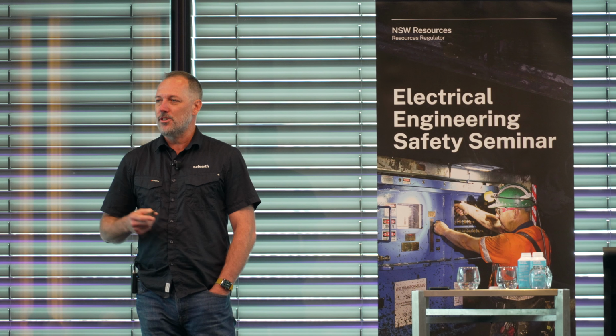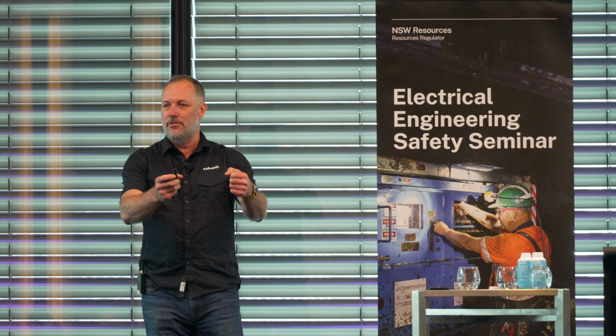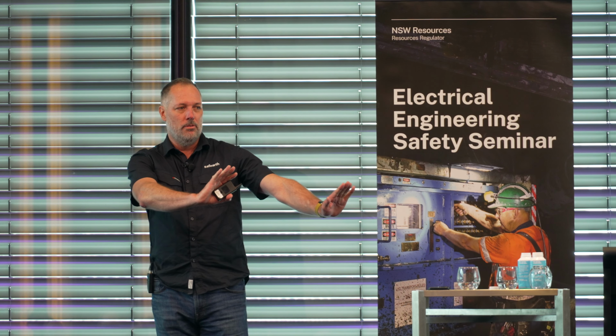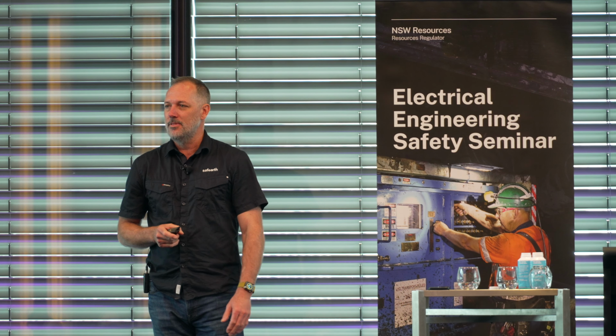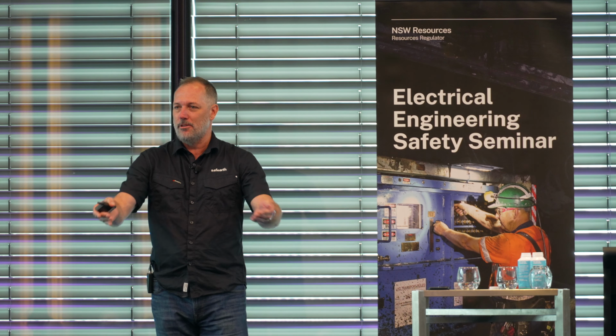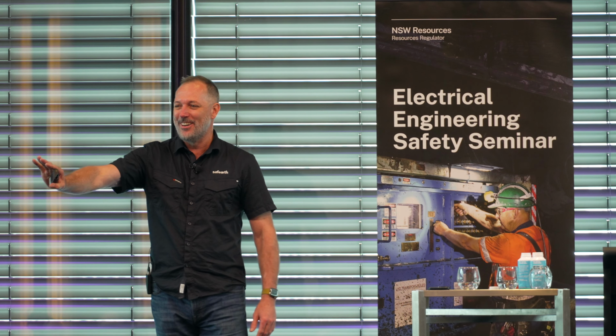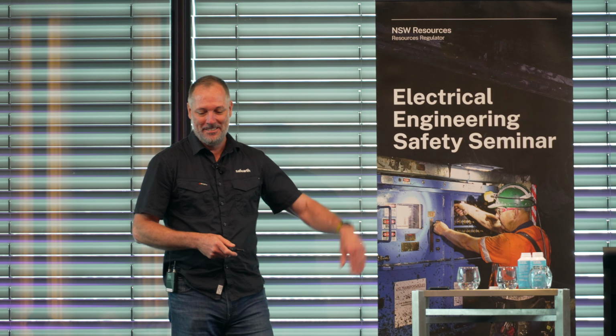NSPs feel like they want to limit their liability, which I find a bit of a conundrum, because they'll agree to a 66 or 132 kV connection, sign all the paperwork, you'll bond up your phase conductors and energise things and off you go. But they'll say, we're not going to create a connected earthing system. We'll give you the electrons, but if they go into the ground, that's your problem, not ours, we don't want them back. They'll get them back eventually - they can't avoid that unless they start doing crazy things like unearthing their transformers.